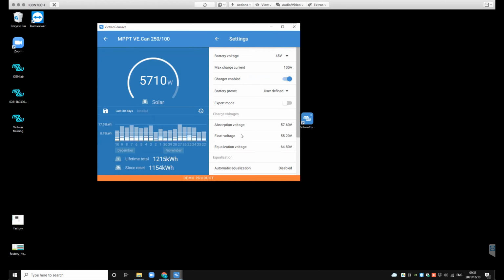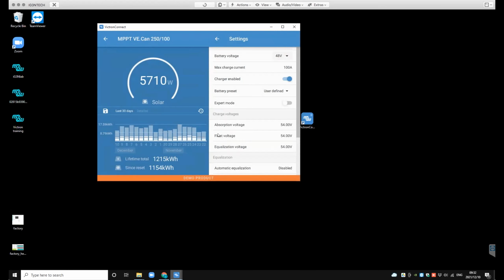Our batteries are quite capable of accepting high charge currents, so most likely 80% of the time you can keep this at maximum of what the MPPT can do. As mentioned, all of our charge set points as a fallback is 54 volts. Make sure that you do absorption, float, and equalization. The BMS will essentially give higher targets than this, and this is just a fallback should that fail.